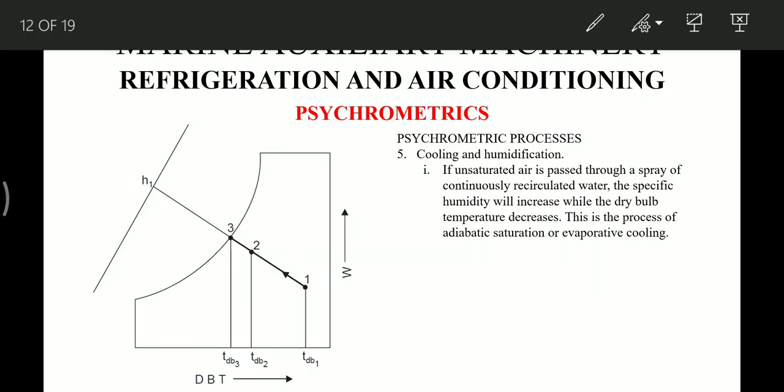The cooling and humidification process occurs when unsaturated air is passed through a spray of continuously circulated water — the specific humidity will increase while the dry bulb temperature decreases. This is the process of adiabatic saturation. As seen in the diagram, the temperature decreases giving a cooling effect while humidity increases, and this process is represented by the corresponding line on the psychrometric chart.